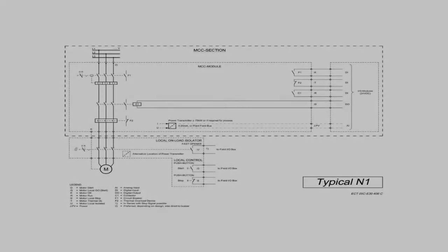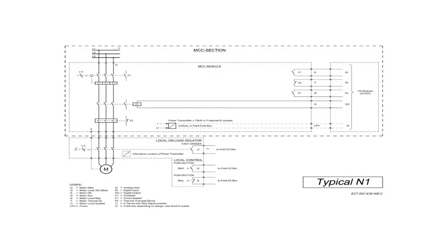Now we will show you a basic single line diagram, where we can put in context how it's connected to an electrical system. On the picture, you can see a typical arrangement for a one-directional motor. The motor is indicated on this single line diagram with an M in a circle on the left bottom side of the picture. On the left upper part, you see L1, L2, L3. These are the three phases, and you can imagine it's installed in an electrical room and supplied to a motor control center called MCC.